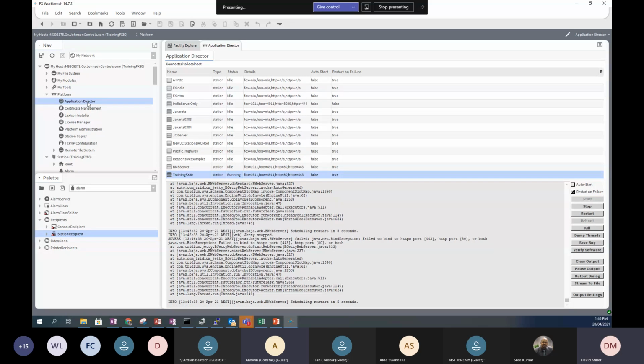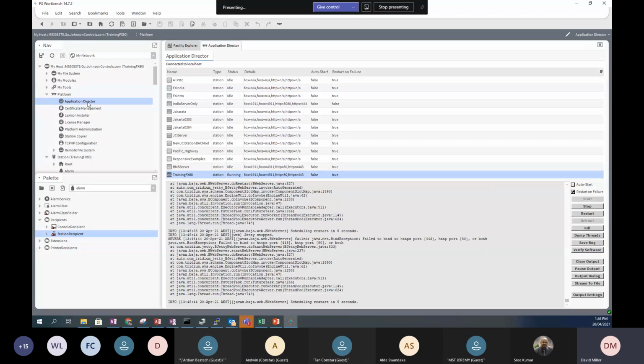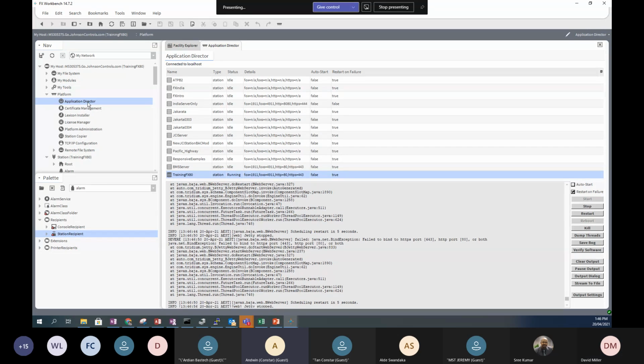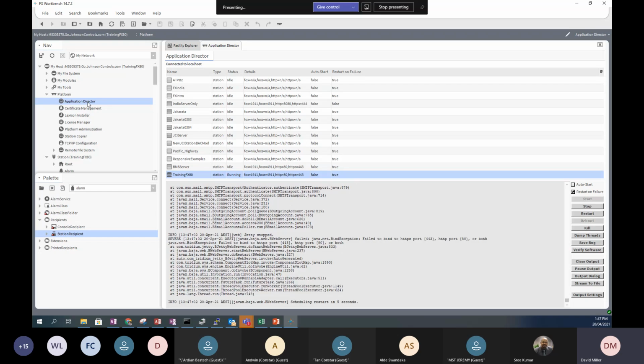Is it one point that's going alarm, normal, occurring a lot, or is it lots of different alarms that all happen at the same time? Lots of different alarms happen at the same time. And they're all acknowledged, and some of them are acknowledged directly, and other ones persist and come back again.